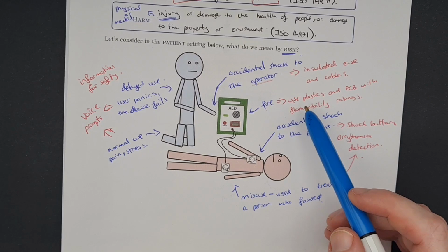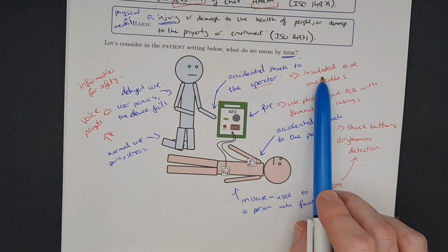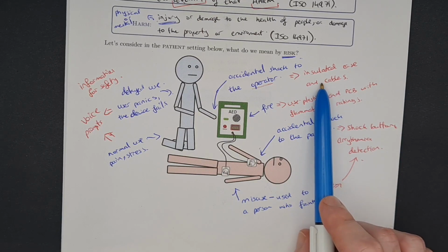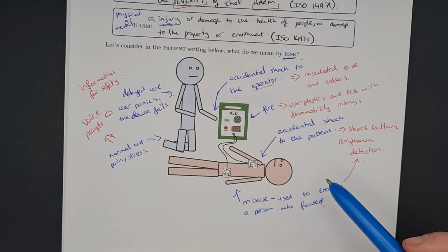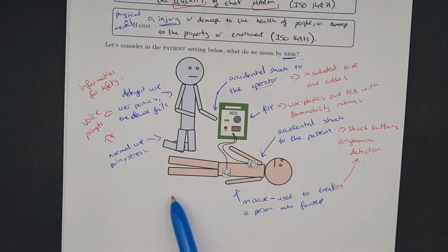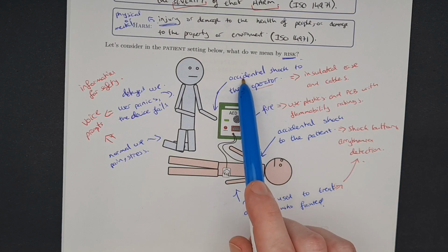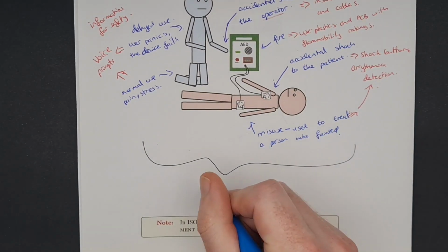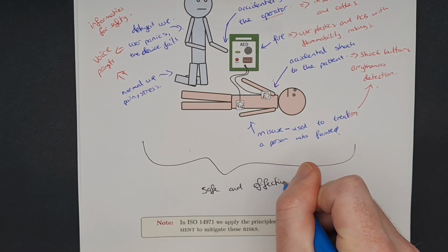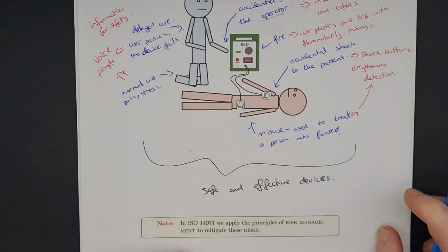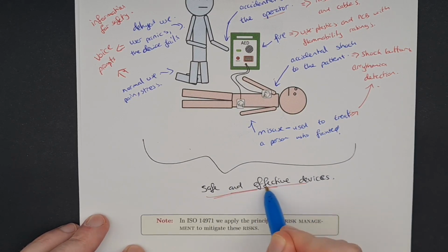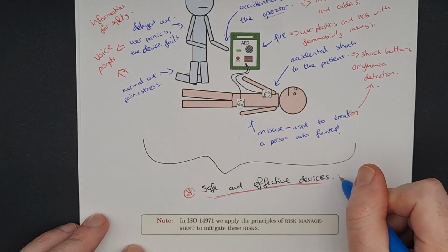The big emphasis really on ISO 14971 is not only introducing risk control measures, but you have to verify that they are in fact effective. And that is something that we'll explore in more detail in later chapters. But hopefully, just this kind of short and sweet story of identify risks and implement risk controls can really show you how risk management can be used with our overall goal to always make more safe and effective devices. And as we will kind of see throughout, risk management is basically just the structured procedure that we apply to achieve this overall goal of safe and effective devices.